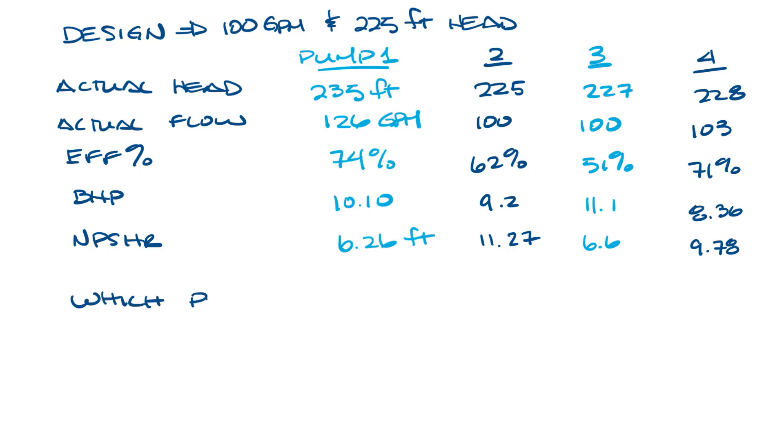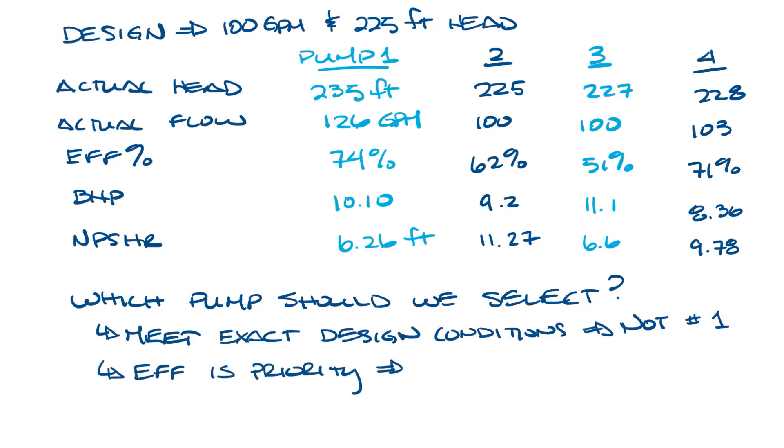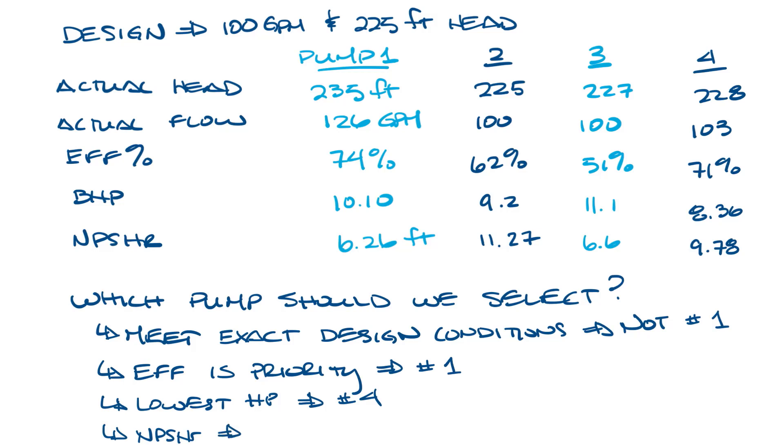So which pump should we select? Well, the answer is it depends. If meeting our exact design conditions is important, then we can eliminate the first pump option. If efficiency is a priority, then we would pick pump one. If it's lowest horsepower we want, then it would be pump four. And if NPSHR is most important, we could choose between one and three.